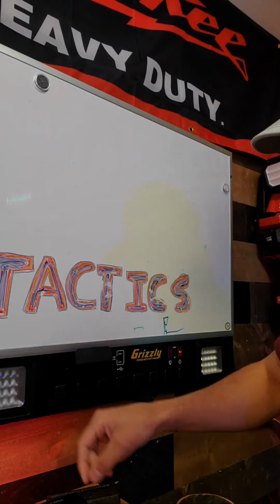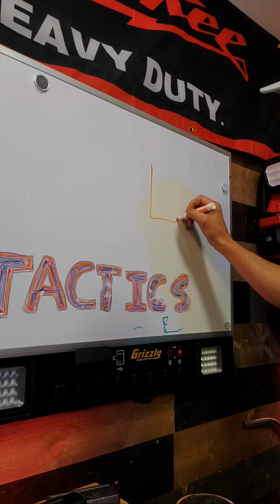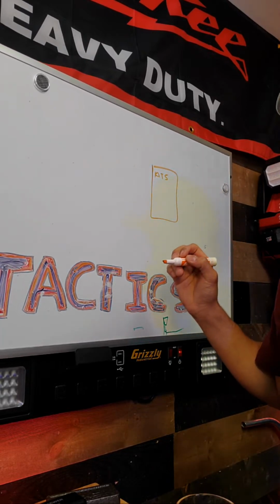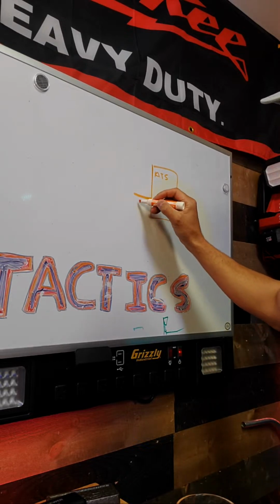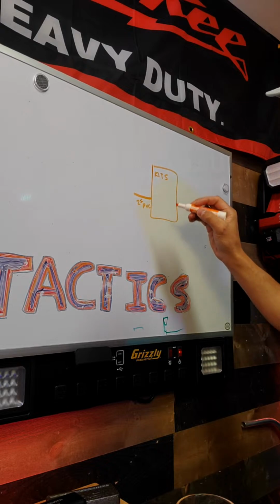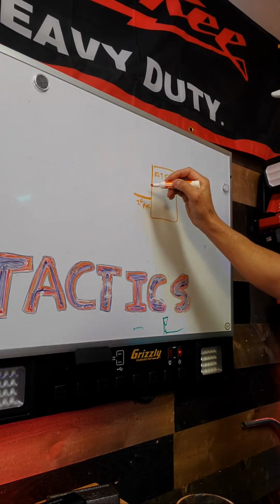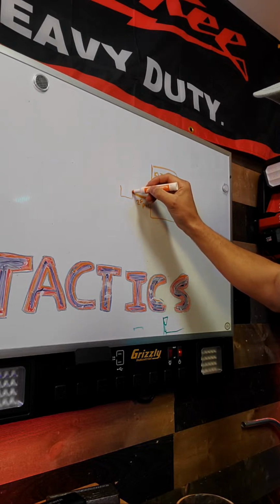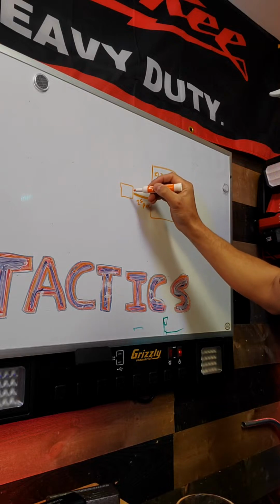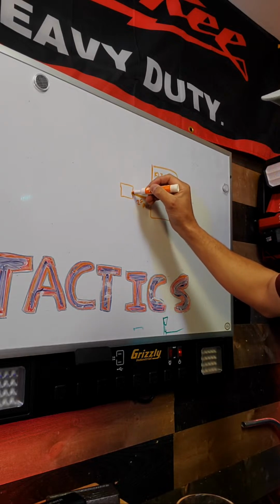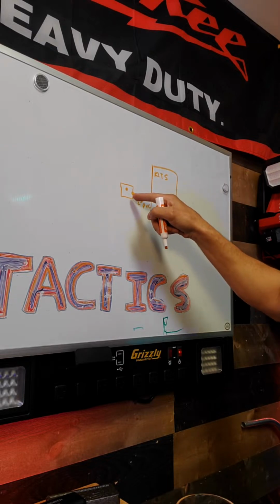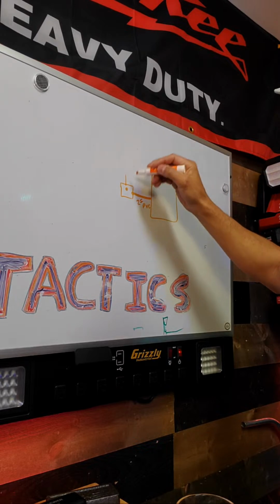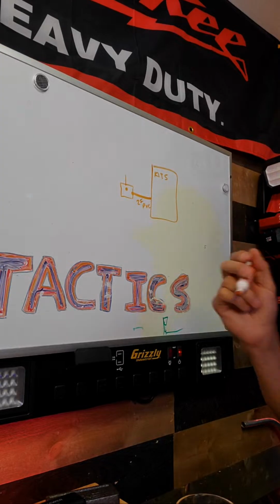I had one where this guy put a 2-inch box into a 6x6, so he put a 2-inch PVC coming out of his ATS. He went through a fence—I'm not going to draw the fence—and came into a box, 6x6 by the way. The hole was here, and it was less than 3 inches away from the other hole. Then he went back into what is now the sub panel inside the house to feed it. Let me zoom in—that was way too much.